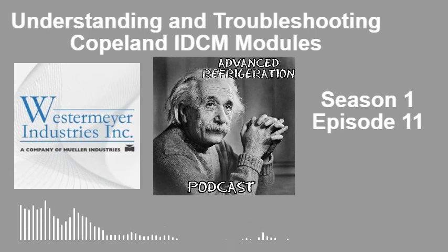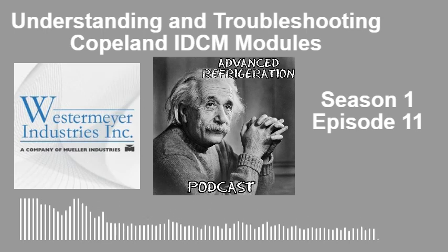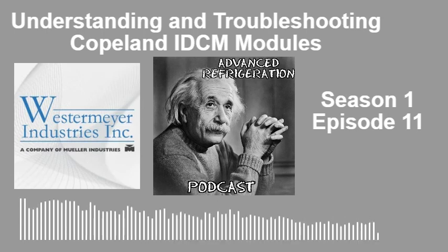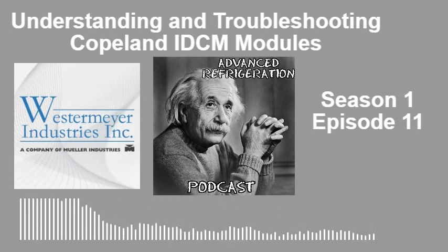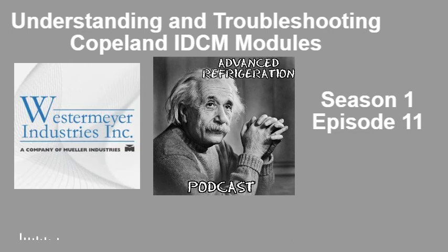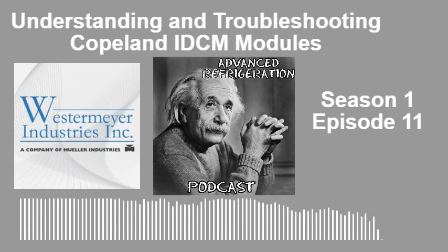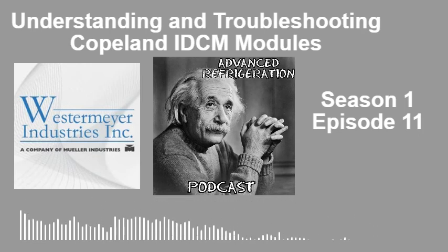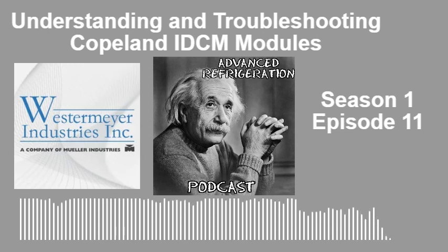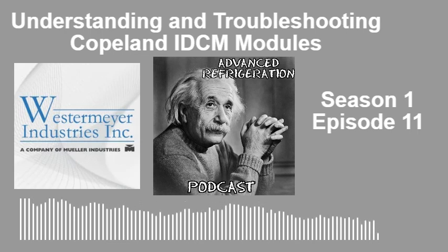Okay, and then the high discharge temperature fault on these locks out at 260. I'm sorry, it locks out at... I can read that. Wouldn't it be like 310? Just like the regular. Yeah, it is. Okay, because it would be comparable to the demand cooling module. Those shut off at 310. They engage the liquid line solenoid at 282 and kick them on at 292 and kick it back out at 282. You might think that that's a high temperature, but you have to remember that the sensors are internal in the head. So I'm not talking about actual discharge line temperature. I'm actually talking about head temperature.